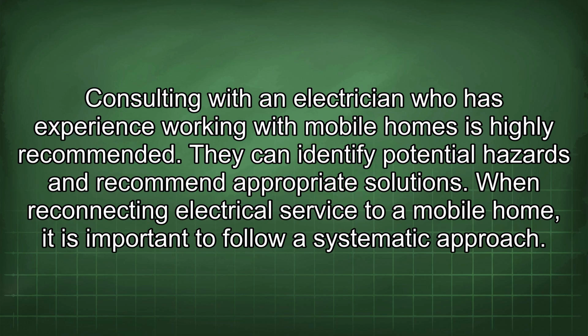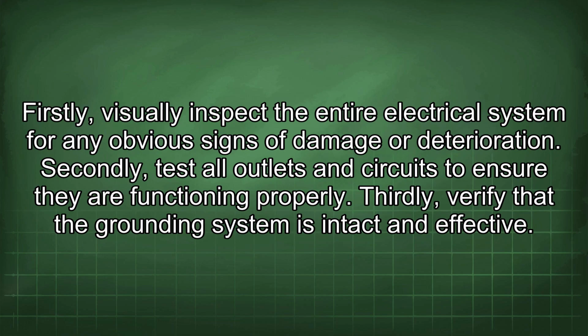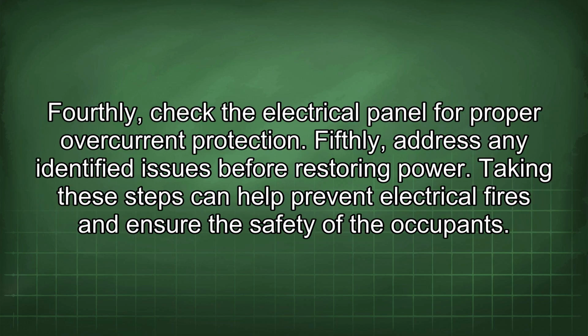When reconnecting electrical service to a mobile home, it is important to follow a systematic approach. Firstly, visually inspect the entire electrical system for any obvious signs of damage or deterioration. Secondly, test all outlets and circuits to ensure they are functioning properly. Thirdly, verify that the grounding system is intact and effective. Fourthly, check the electrical panel for proper overcurrent protection. Fifthly, address any identified issues before restoring power. Taking these steps can help prevent electrical fires and ensure the safety of the occupants.